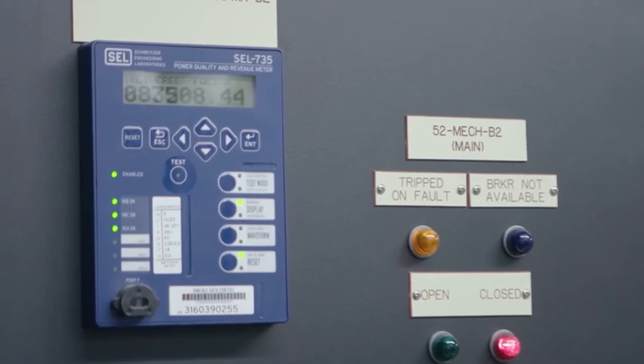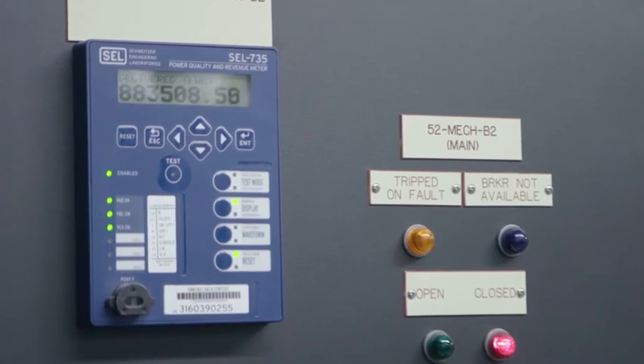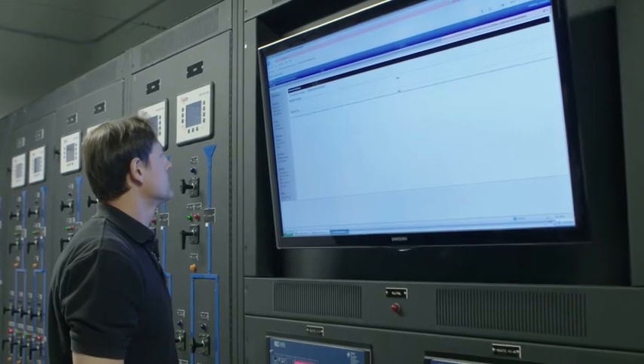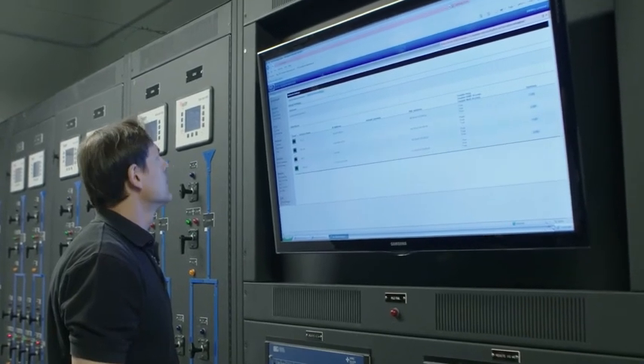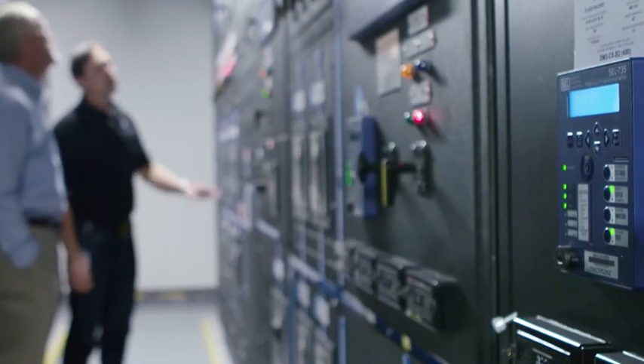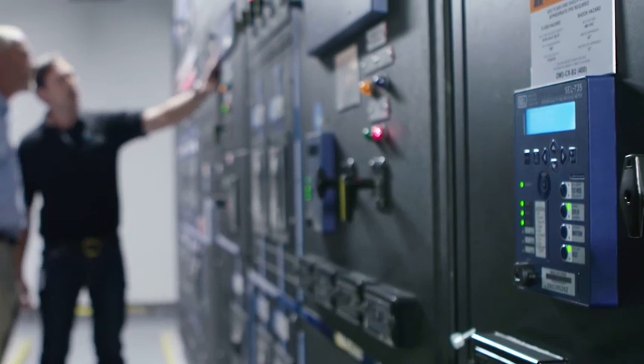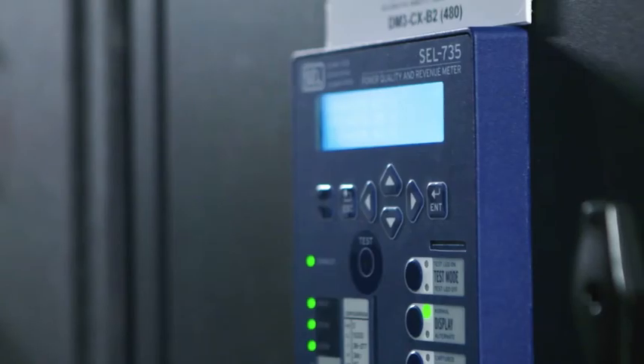The meter is actually very easy to program. It comes out of the box with almost all the BMS, EPMS integration settings right where they need to be. Essentially plug in the PT and CT ratios, and it just takes off and works.